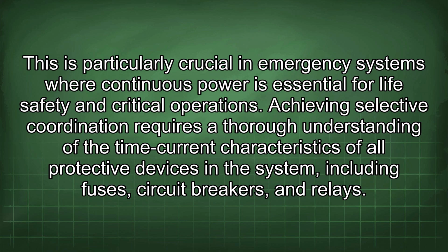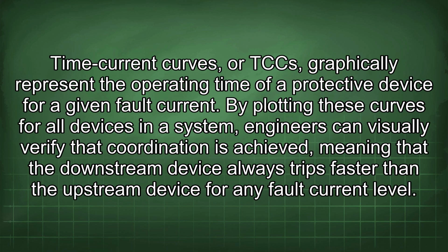Achieving selective coordination requires a thorough understanding of the time current characteristics of all protective devices in the system, including fuses, circuit breakers, and relays. Time current curves, or TCCs, graphically represent the operating time of a protective device for a given fault current. By plotting these curves for all devices in a system, engineers can visually verify that coordination is achieved, meaning that the downstream device always trips faster than the upstream device for any fault current level.